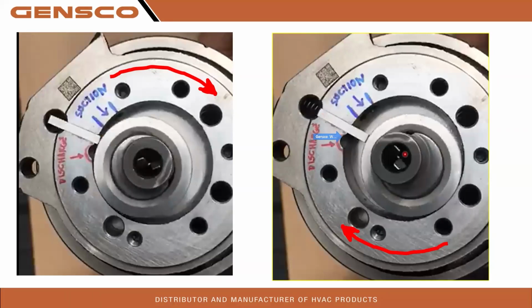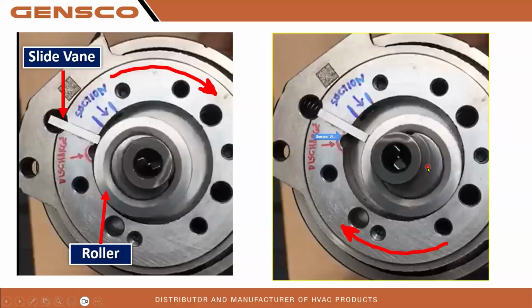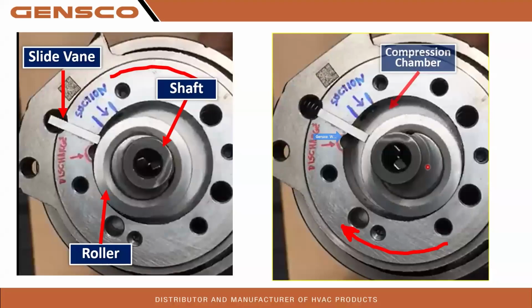In this frame, the roller is on the opposite side of the compression chamber, and the slide vane has slid out of its recess, making contact with the roller and maintaining compression on the high side. So this rotates in a clockwise rotation on this side, and on the upper side, it's counterclockwise rotation, relative to the roller and shaft. That is the slide vane. That is the roller. That is the shaft. Here is the compression chamber.